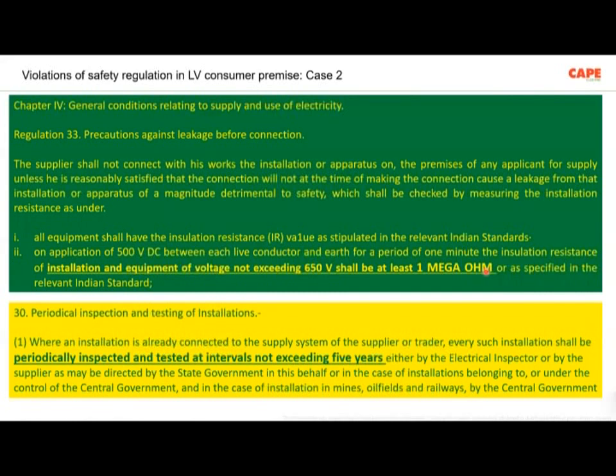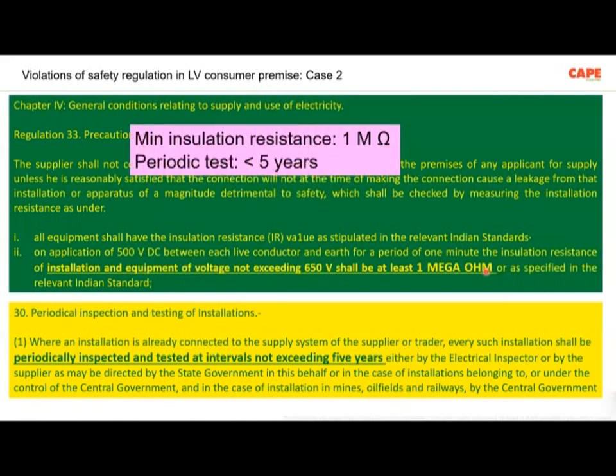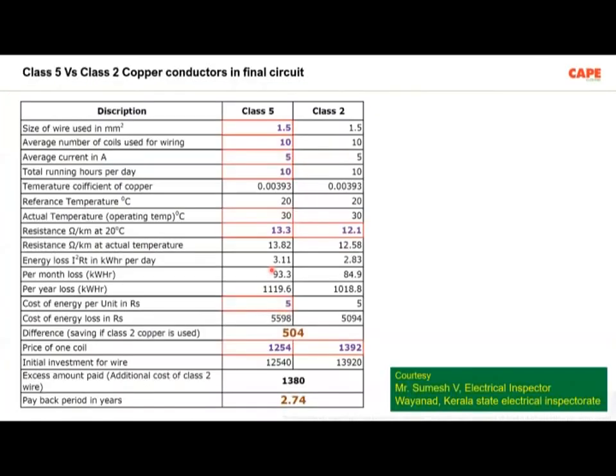Also, regulation 30 says every 5 years the power supply company is supposed to do this particular testing and ensure that the insulation resistance is higher than 1 mega ohm. If the insulation resistance is higher than 1 mega ohm, the chance of accidents is quite less. Now, regarding these regulations, I had discussions with a lot of electricity supply companies, and in fact, the old engineers know about the regulation, but the new generation engineers don't even know about this requirement. As a result, such tests are never carried out by the electricity supply company, not across India, but in most of the places.